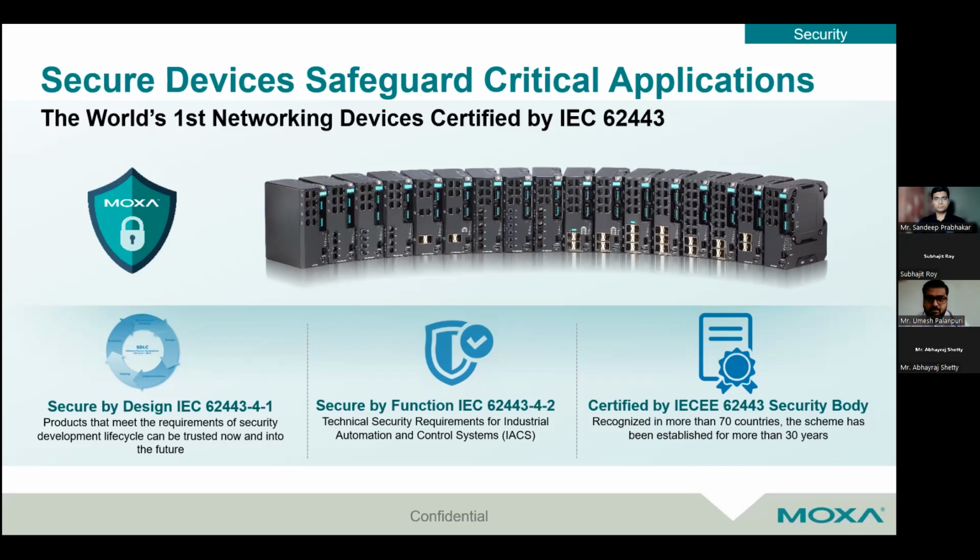One more question we have from Mr. Nitin: does it support the Profinet protocol to push the data from Siemens PLC, or is any protocol converter required? So I'll answer. Profinet is based on Ethernet protocol, and all of our switches and systems run on Ethernet, so it really does not matter what kind of protocol is being transmitted to the switch. It can transmit Profinet, Modbus, Ethernet IP, any other protocol, and it can get updated onto your PLC or SCADA system. The switch doesn't actually read Profinet. While our switches can be managed through Profinet from your SCADA, where you can access the Profinet addresses in our switch to manage and check its status, the passing of data through the switch is completely transparent. It just checks the Ethernet frame and transmits it onto the SCADA or PLC system. The application level is not a concern for the switch or the networking.